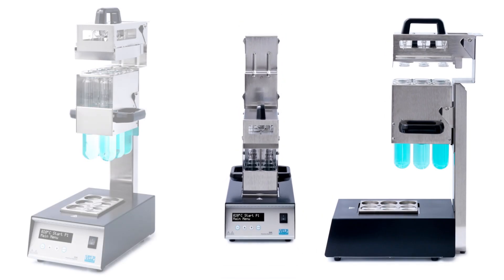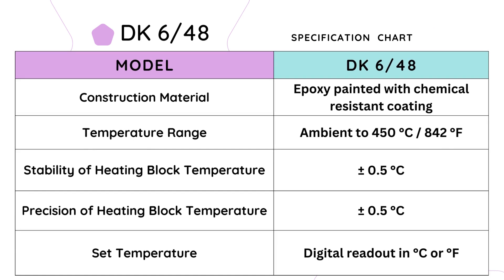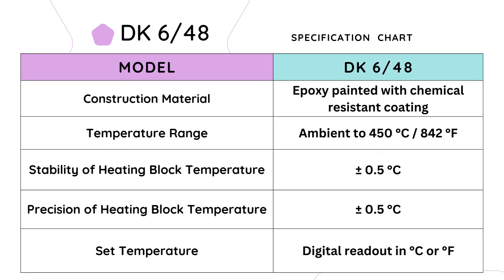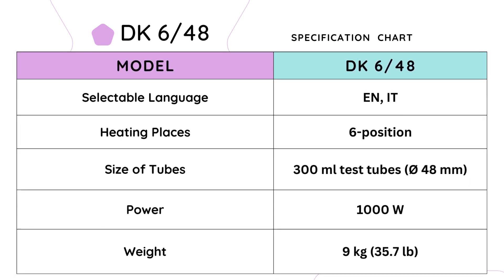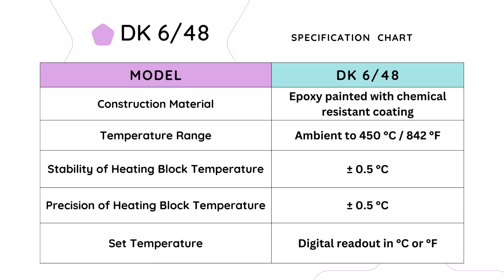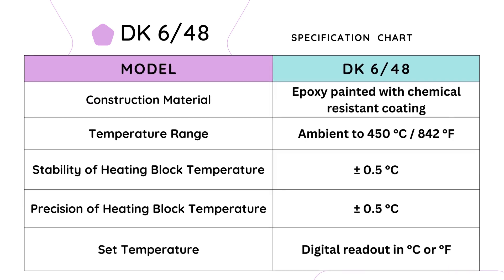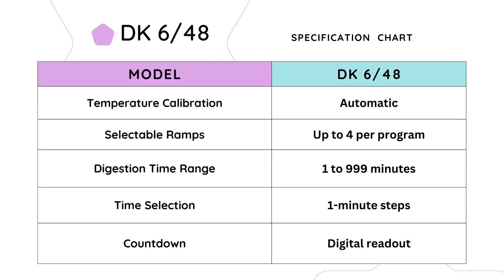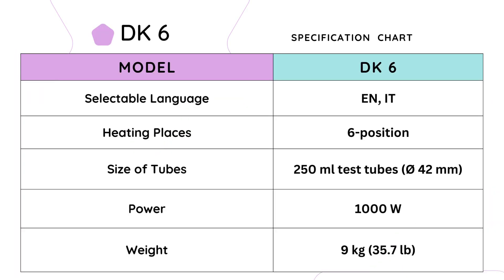Now let us review the specifications for the semi-automatic digester DK 6/48. The DK 6/48 model shares the same specifications as the DK6 model, with the only distinction lying in the size of the tubes it accommodates. Instead of the standard 250 ml test tubes with a diameter of 42 mm, the DK 6/48 is designed to accommodate 300 ml test tubes with a slightly larger diameter of 48 mm. All other specifications — including construction material, temperature range, heating block stability, selectable ramps, digestion time range, power, weight, and dimensions — remain the same as the DK6 model.